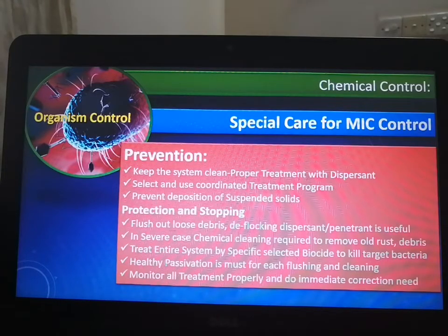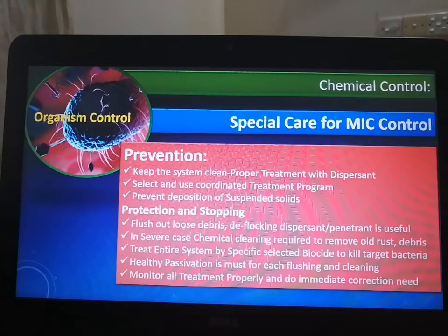Finally, we must take care of microbial induced corrosion (MIC) control as part of microorganism control. To keep the system free of MIC, we have to take two kinds of special measures. One is prevention, so the system is proactively protected from the chance or probability of MIC. If we understand some MIC has already developed, we have to protect and stop further deterioration. For prevention of microbial induced corrosion, the fundamental thing is the system must have treatment with dispersion, biodispersion, meaning we need to keep the system clean.